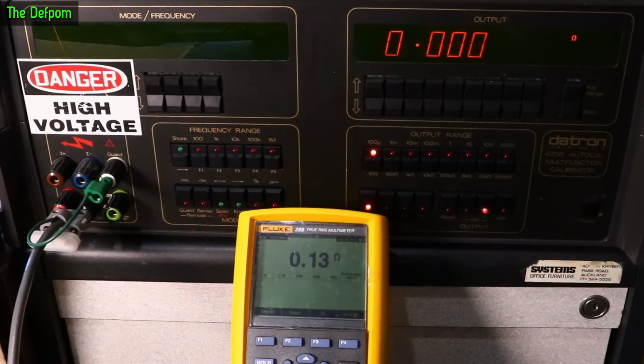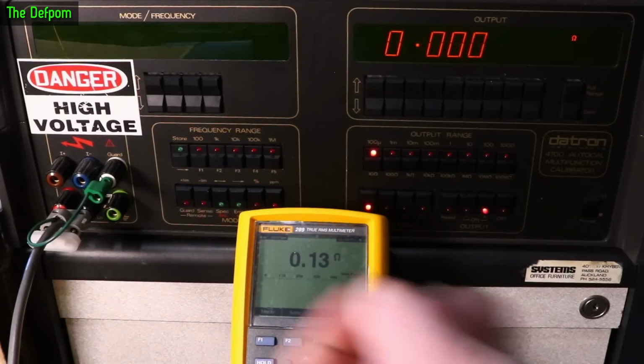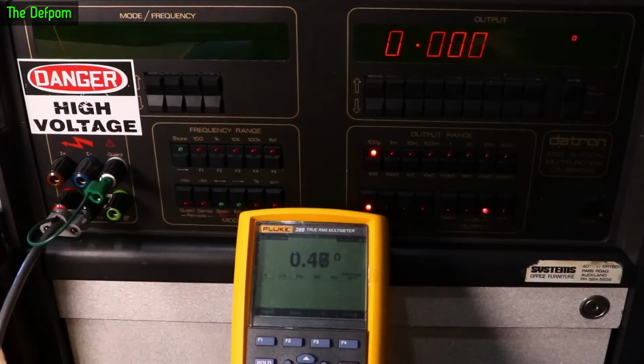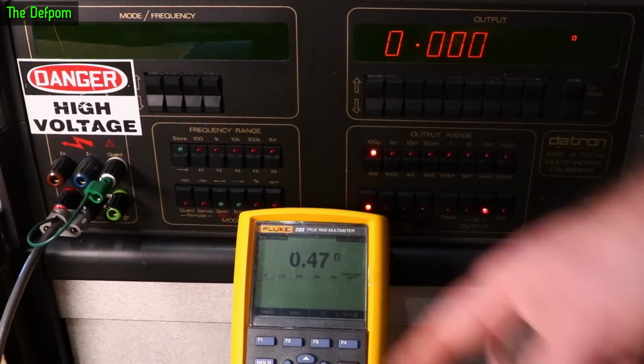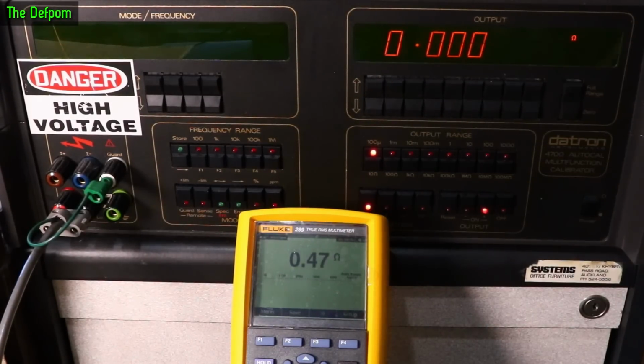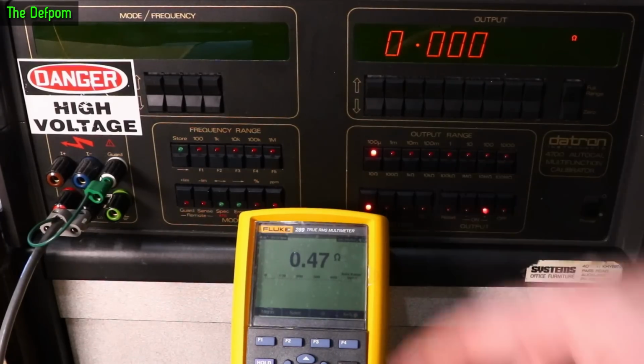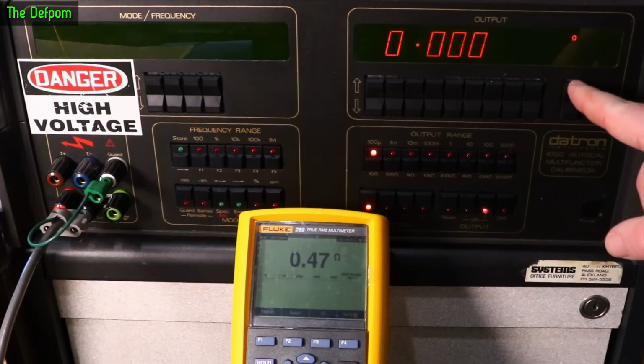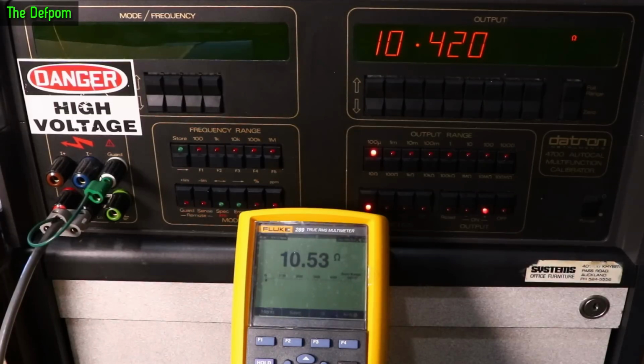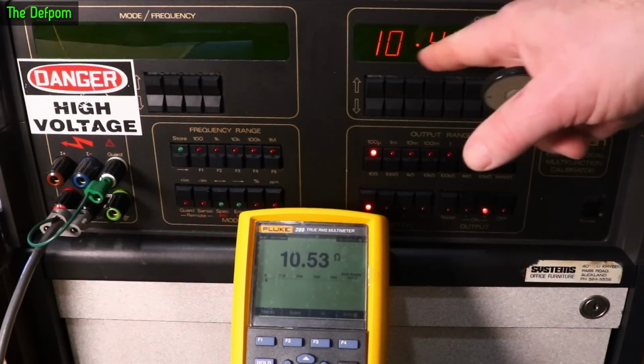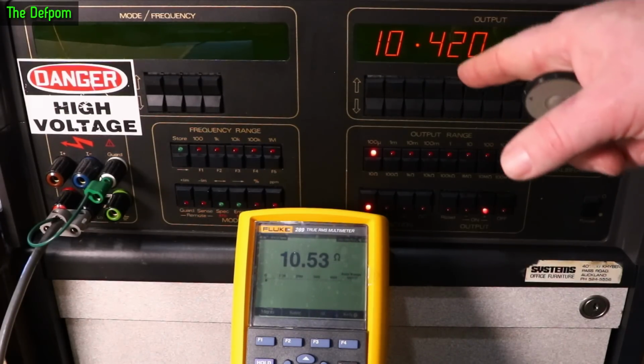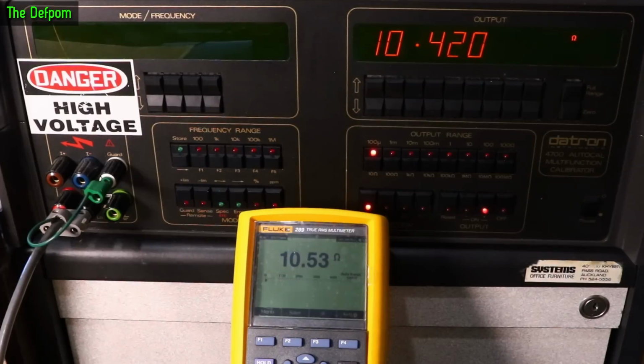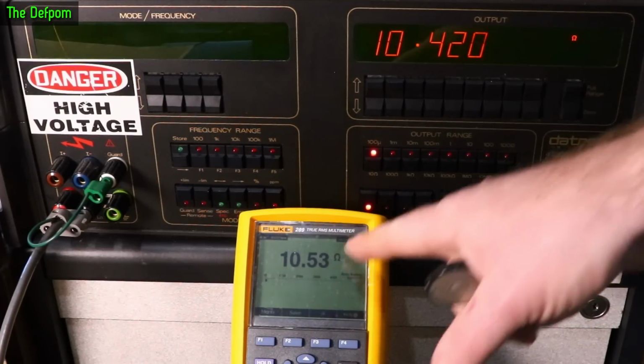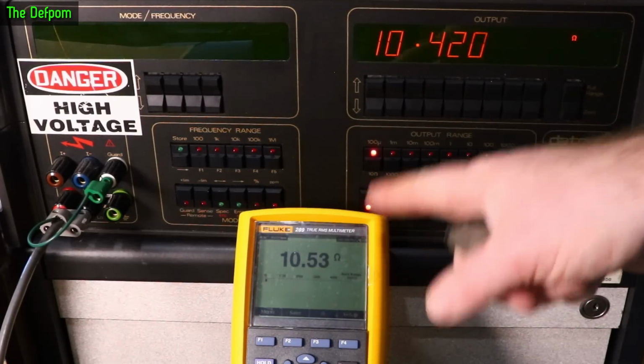And back on resistance mode, we're getting about 0.13 ohms as a short directly on the input to the calibrator, or the output of the calibrator. And obviously, so we're getting about 0.3 ohms through the calibrator circuitry. We could null that out. I'm going to leave it as is. So, 10 ohms. Well, we've got 10.42 here. Don't forget we've got a slight offset of 0.4, which isn't really factoring in here. This may actually be accounting for that offset.